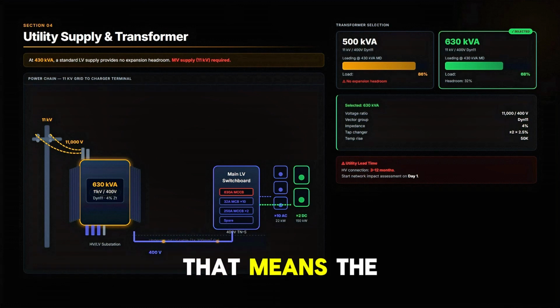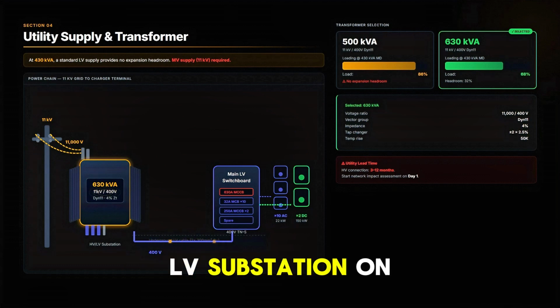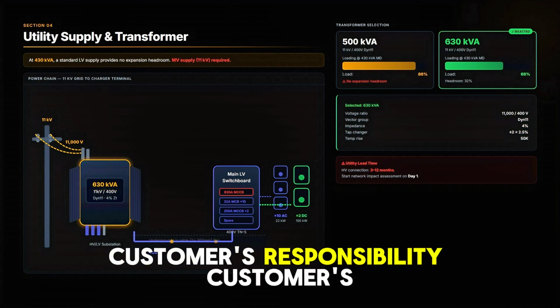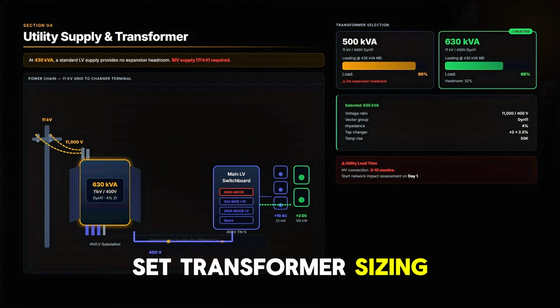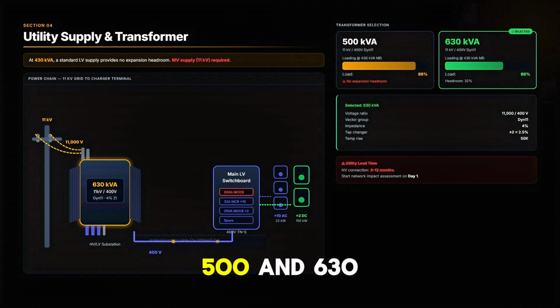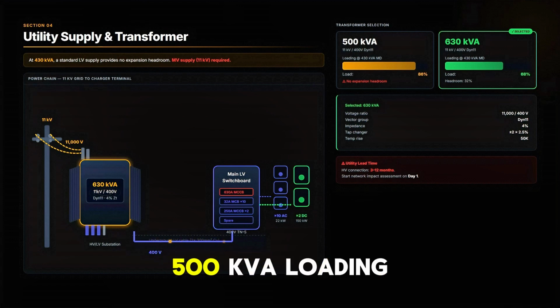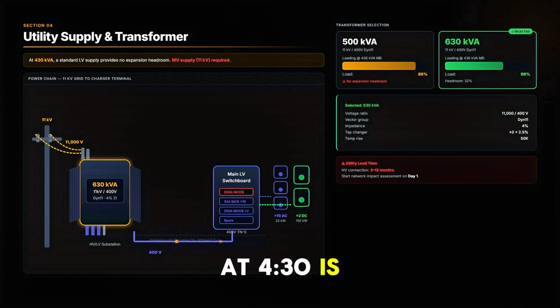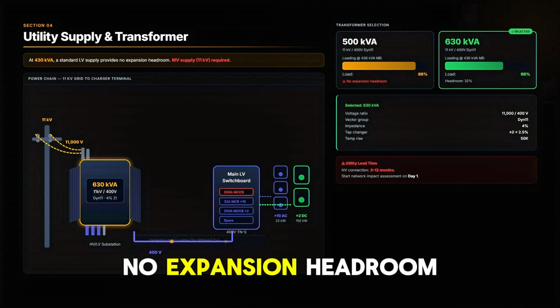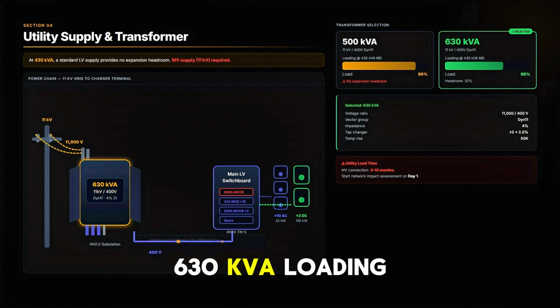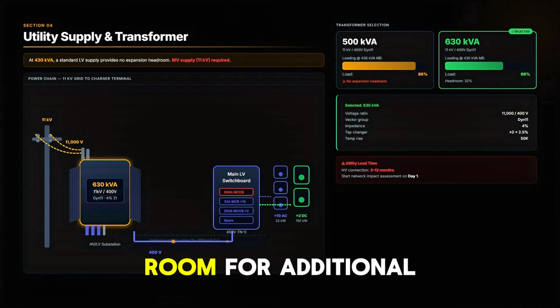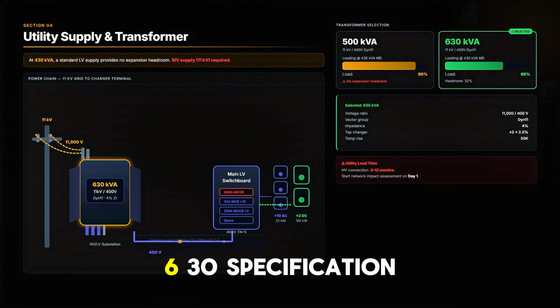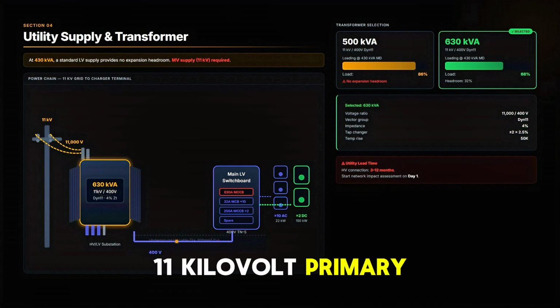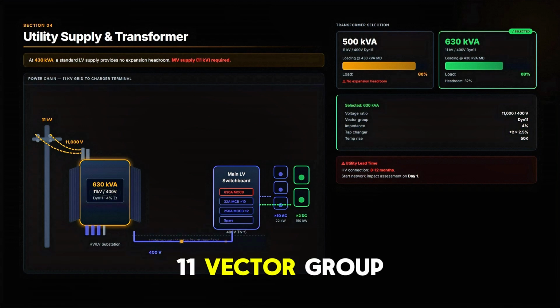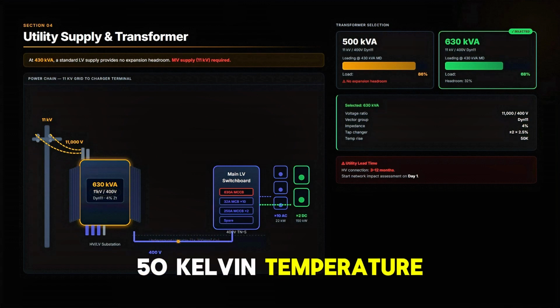11 kilovolts. That means the customer installs their own HV/LV substation on site, transformer, HV switchgear, LV switchboard, customer's responsibility, customer's asset. Transformer sizing. Next standard sizes are 500 and 630 kilovolt amps. 500 kVA, loading at 430 is 86%, tight, no expansion headroom. 630 kVA, loading at 68%. Comfortable, room for additional chargers in stage 2, we select the 630. Specification: 11 kilovolt primary, 400 volt secondary, Dyn11 vector group, 4% impedance, 50 Kelvin temperature rise.